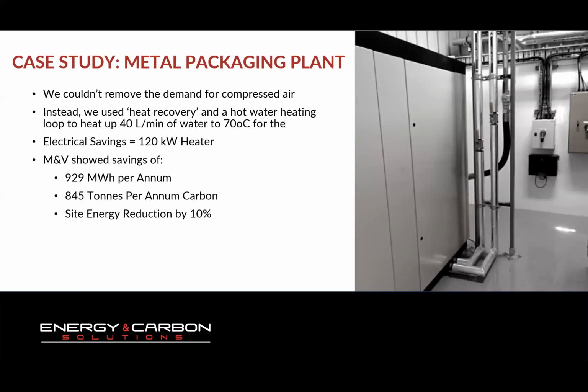So what we actually did, we couldn't actually remove any of the demand for compressed air on that site because of the way that the plant ran. So instead what we did is we redesigned it with a heat recovery loop, and we produced 40 litres of water a minute at 70 degrees for the plant. The electrical savings, we reduced the consumption on site by turning off the 120 kilowatt heater. So therefore they could preheat, and you can see the piping on the right-hand side there.